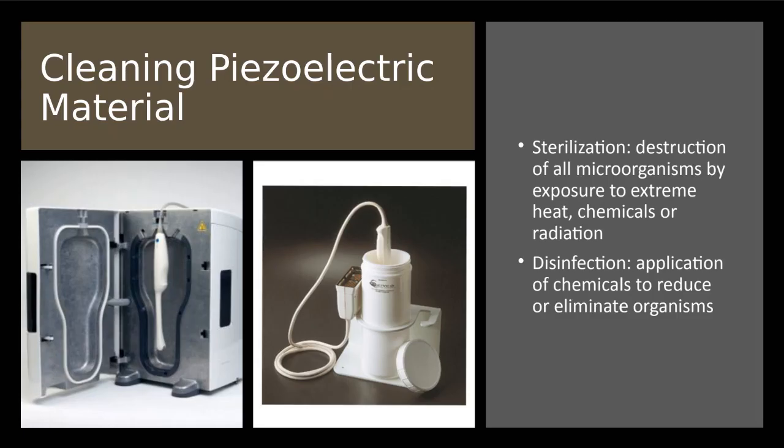On that same topic, when we're cleaning our transducers, we've now learned that this piezoelectric material is the really important part of the composition of our transducer, and we don't want to apply too much heat to it. So how are we going to be cleaning our probes? We want to be aware of that.